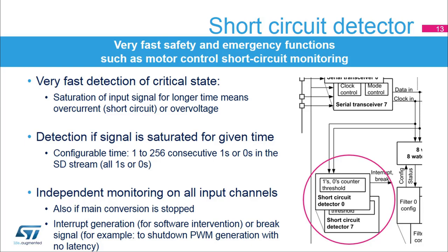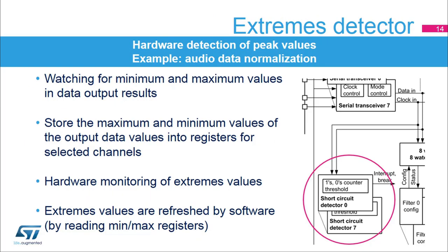The extremes detector monitors output results and stores the extreme values into minimum and maximum registers as well as the associated channel number. Monitoring of data for extremes is only performed on selected channels to ensure that channels do not mix different input levels. Stored extreme values are refreshed each time the values are read in the register.